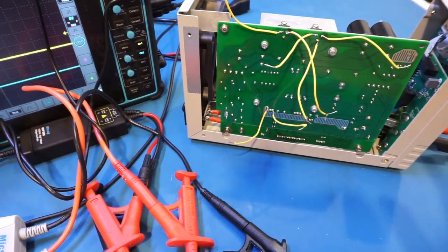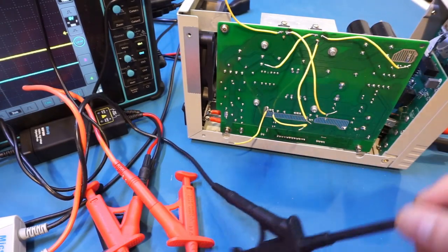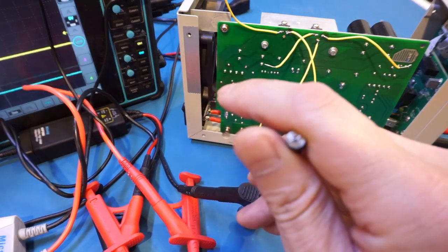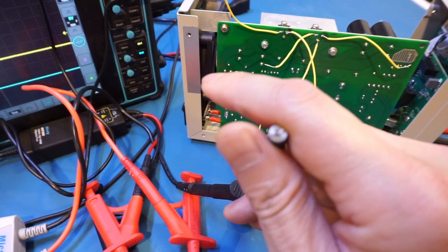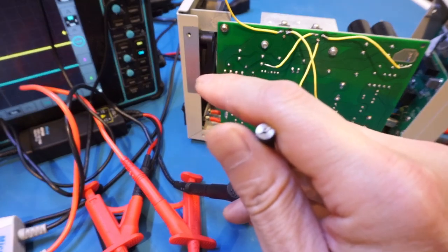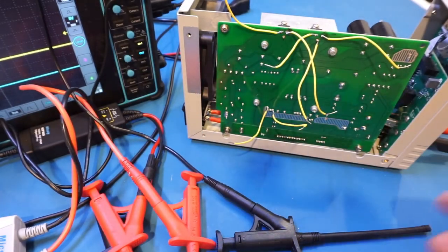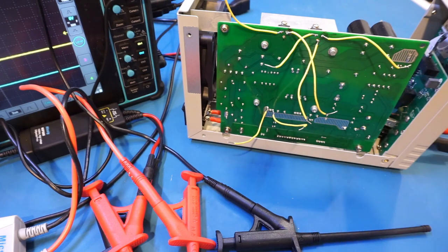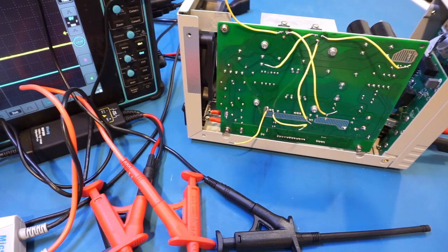I soldered some wires onto the board so we can hook up the differential probes. Now, these grabbers are fairly large, and they have metallic tips, so you don't want to directly hook them onto the MOSFETs. Anyway, this setup will cause some signal degradation in the drive waveform, but not a significant impact.